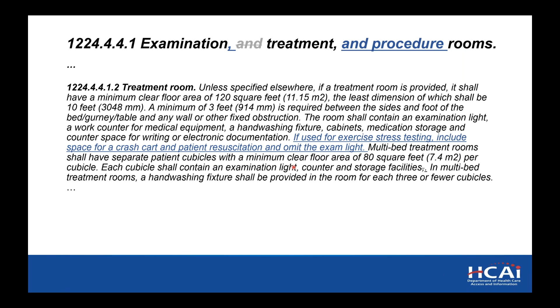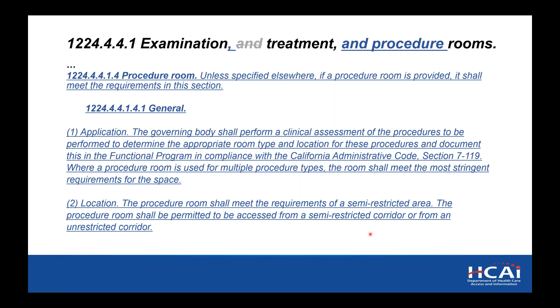Then we have all the requirements for a procedure room. I'm not going to go through them all. If a procedure room is provided, it shall meet these requirements. And here's where we have the location: the room shall meet the requirements of a semi-restricted area. So the room itself needs to be semi-restricted, but the procedure room shall be permitted to be accessed from a semi-restricted or from an unrestricted corridor. So again, if we're going into just a larger type treatment room, you can have it where it's not in the operating environment.